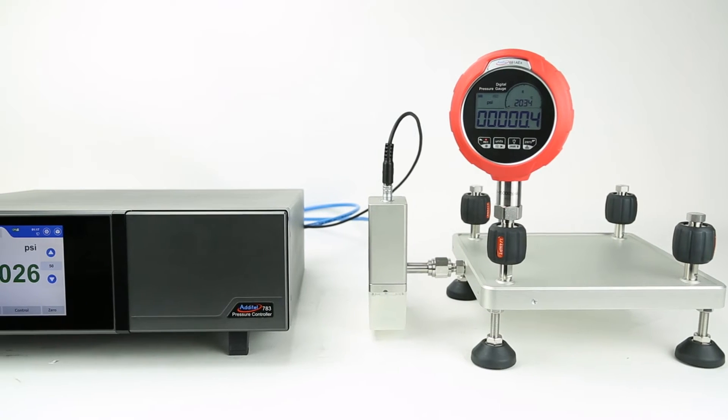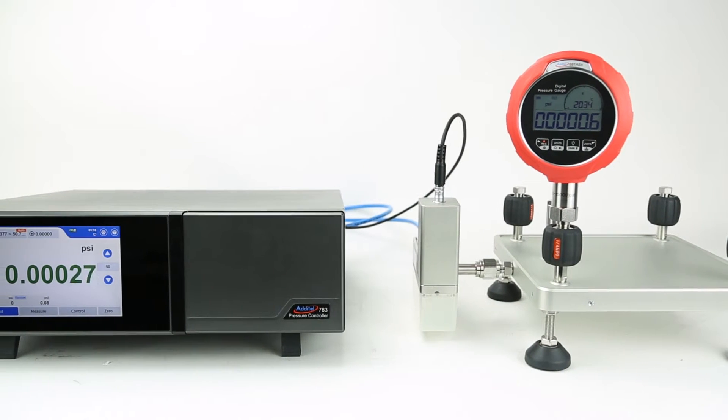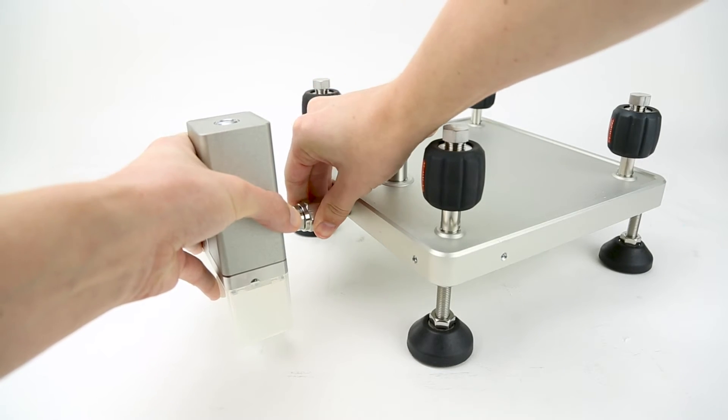This optional accessory is easy to set up and integrate into your Additel calibration system. First, attach the CPS directly to the external manifold that your pressure devices will be connected to.